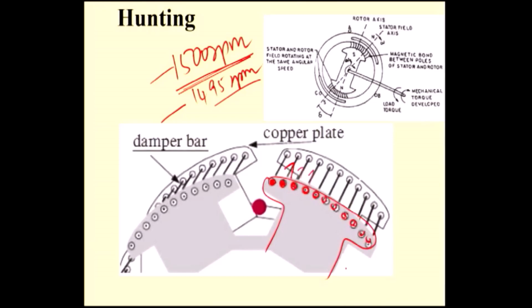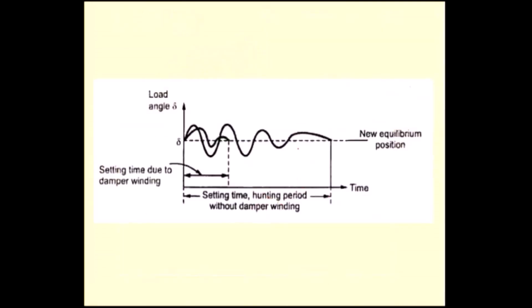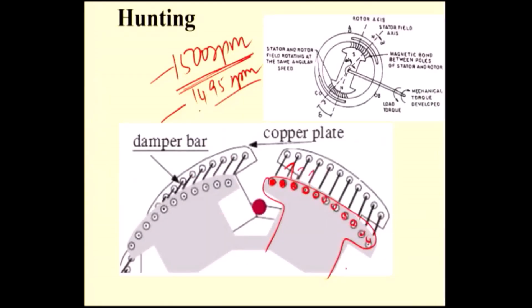The rotor flux increases, which means the rotor once again goes back to synchronism — pulled into synchronism. Now the delta value is less compared to the previous case. Without damper winding, oscillations persist. If you have damper winding, the oscillation is immediately removed. This delta is called the load angle. Once the rotor runs at the same speed as the rotating magnetic field, there is no current in the damper winding. The damper winding will only carry current when the rotor tries to come out from synchronism — for example, when the load is suddenly increased.